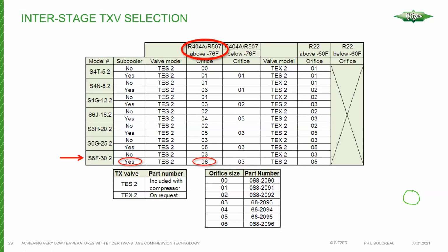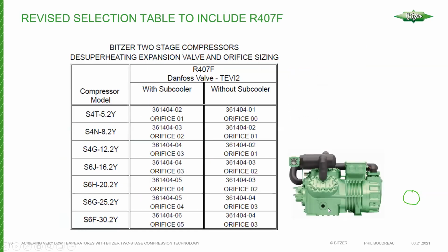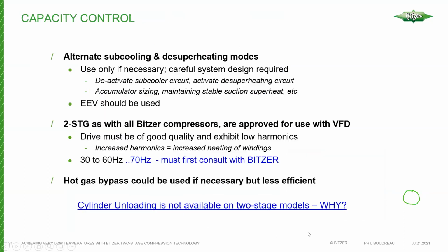And if you're not using the subcooler, that implies that you're using the compressor in a desuperheating only mode. In this case, you'd use the 03 orifice. There's also charts available for 407C, 407F, also available for 448, 449. For capacity control, you could alternate subcooling and desuperheating modes, but please consult us if you're ever considering doing something like this. You have to be very careful when you're switching modes.